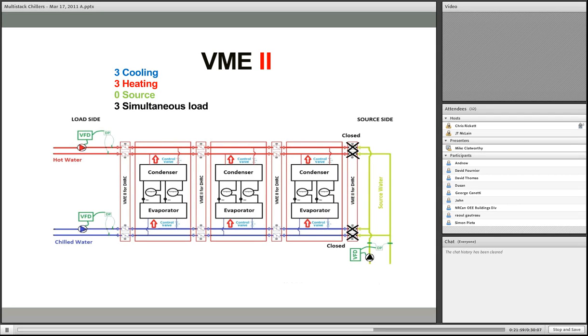And then in this one, it's equal. I've got 3 in heating, 3 in cooling, so I've got 3 modules worth of simultaneous load. This is the most efficient example, and I've closed all the valves to the source sink, to the geothermal well field, and I'm taking all the heat from the chilled water load and putting it into the hot water load. And I've done that directly without ever having to do reversing valves or reverse the flow of water or refrigerant through any of the heat exchangers.